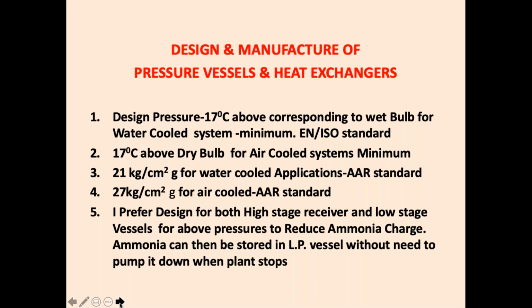17 degrees above dry bulb for air cooled application. If your ambient is 40 or 42 degrees centigrade, then design temperatures should be 57, 58 degrees centigrade. In our AAR standard, we have taken 21 kg per centimeter square to suit Indian conditions, and 27 kg for air cooled application. These pressures are different from the ASHRAE or IIR standard. They indicate much lesser pressures, 20 kg for discharge and 15 or 17 kg for low side, etc. That is not acceptable in India. Our pressures are much higher.